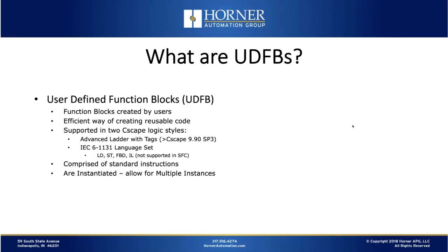Now keep in mind, there's only one version of Cscape, and if you're configuring screen graphics or configuring I/O, setting up communications and networking, that's the same regardless. However, we do give you some choices when it comes to programming your logic. There's the traditional advanced ladder, which is register-based. So with that option, you need to map your variables to registers. And that option has been around the longest and does not support user-defined function blocks.